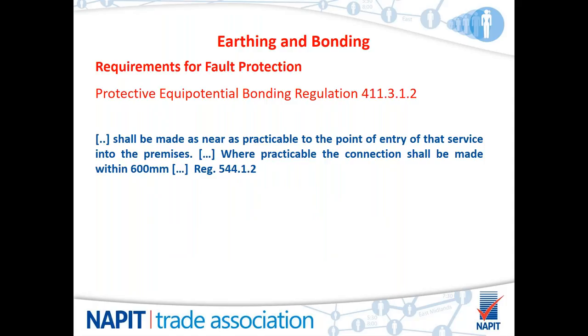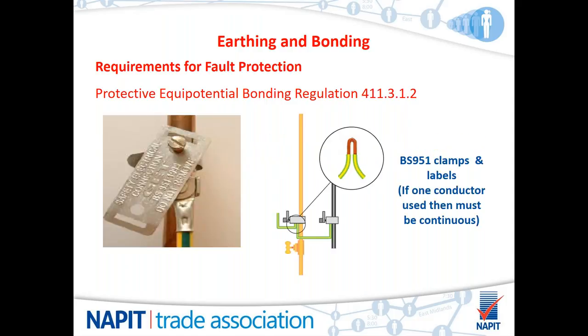Back to the protective equipotential bonding regs, 411.3.1.2 states that everything should be bonded. Later on in BS 7671, Chapter 54 refers to earthing and bonding, and one of the regulations in there states that a protective equipotential bonding conductor shall be made as near as practicable to the point of entry of the service into the premises, and wherever practicable, the connection shall be within 600 millimetres of the stopcock, gas meter, whatever.